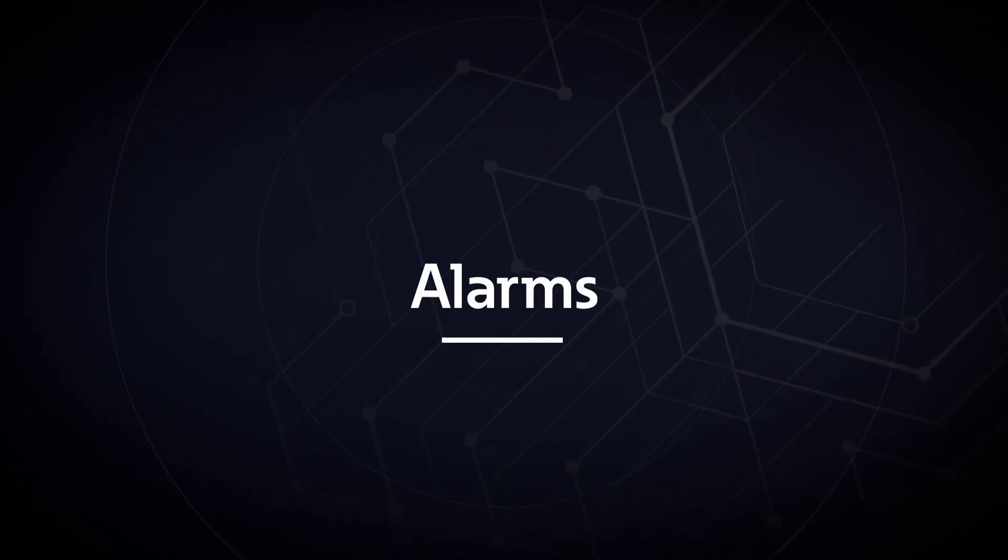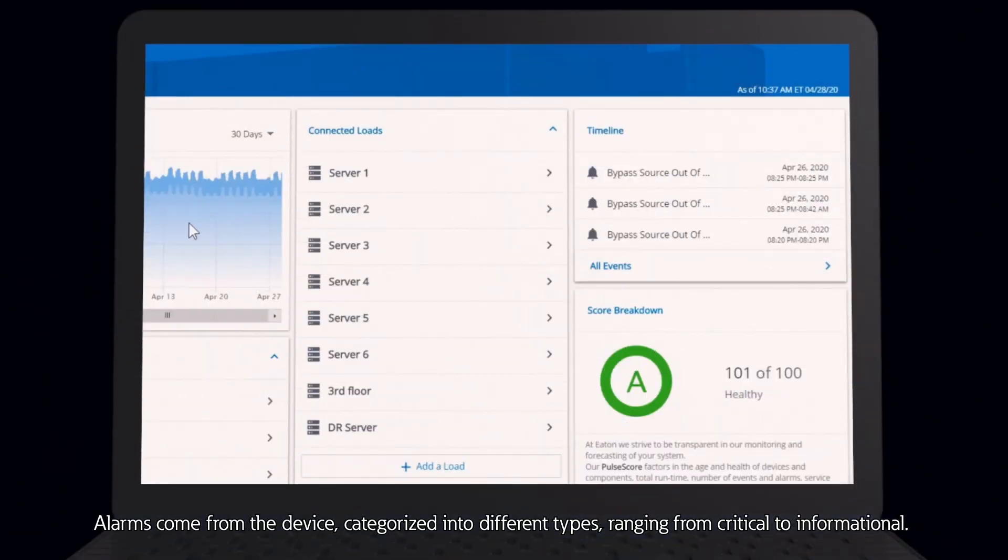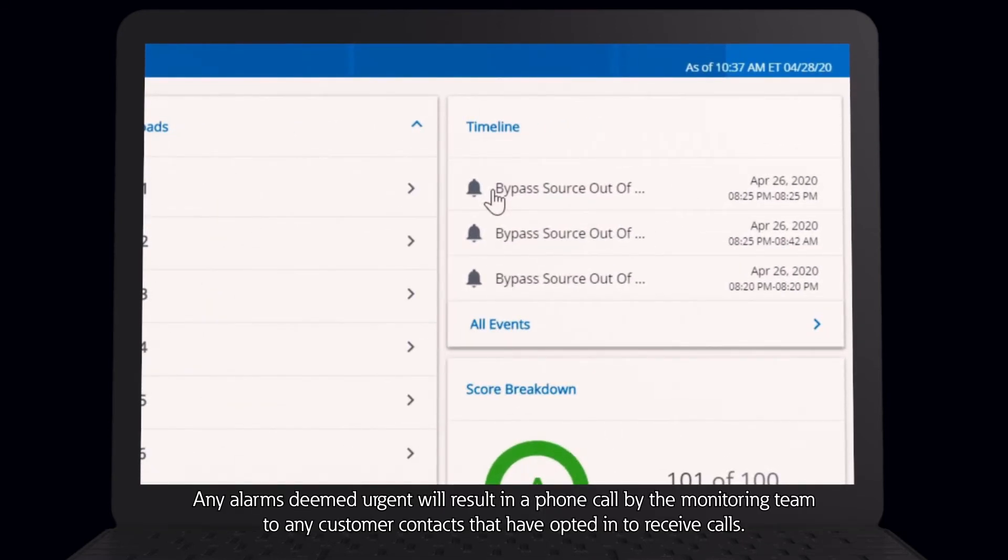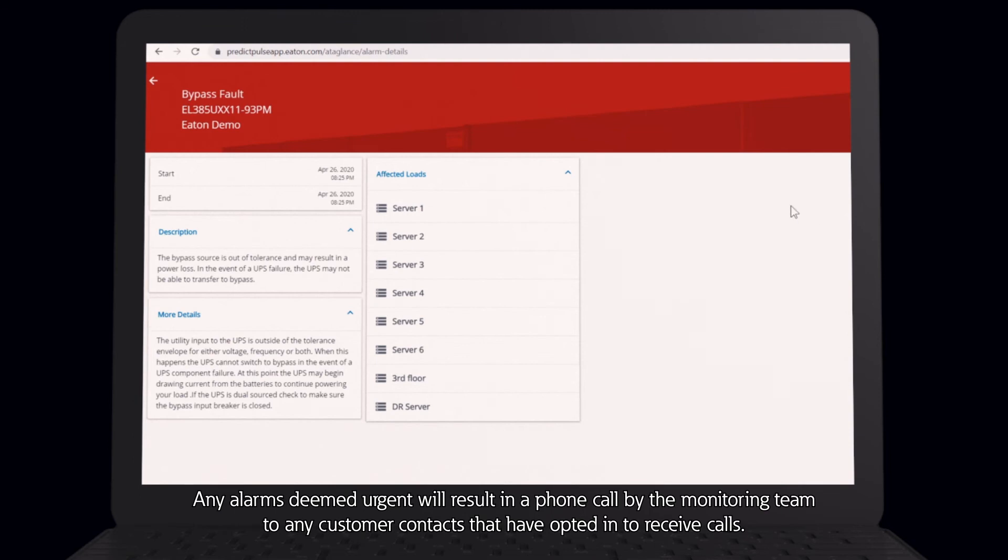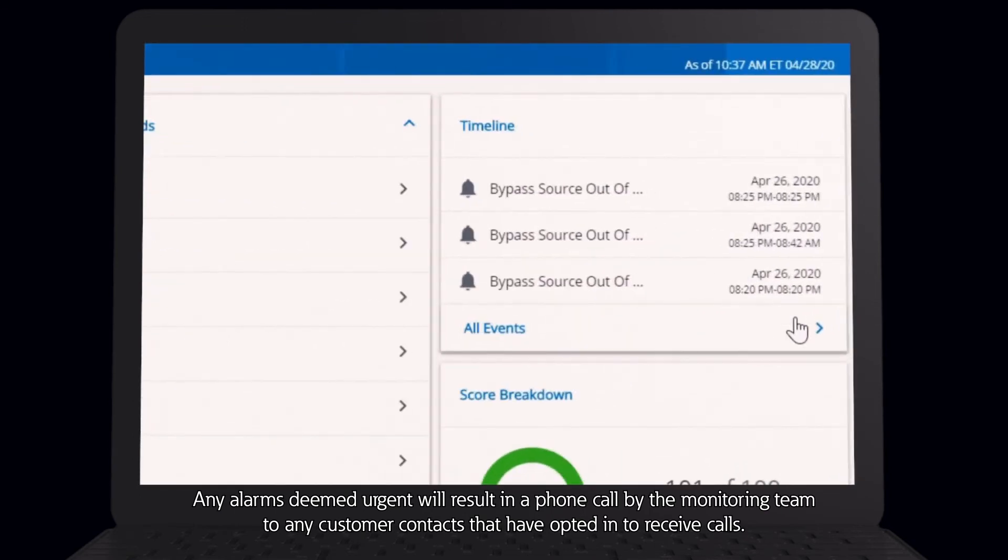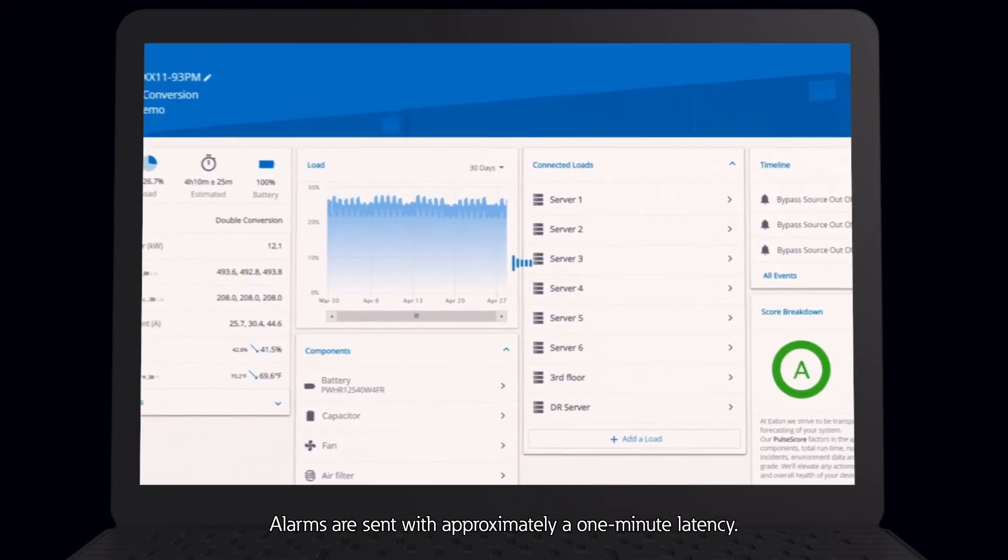Alarms come from the device, categorized into different types ranging from critical to informational. Any alarms deemed urgent will result in a phone call by the monitoring team to any customer contacts that have opted in to receive calls. Alarms are sent with approximately a one minute latency.